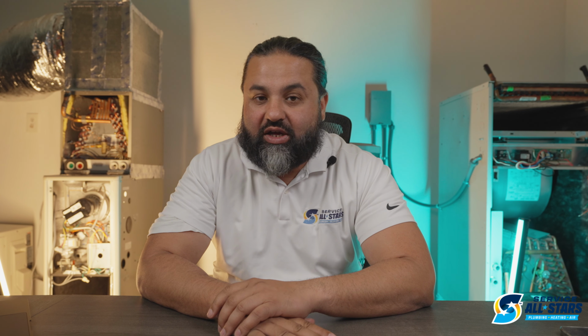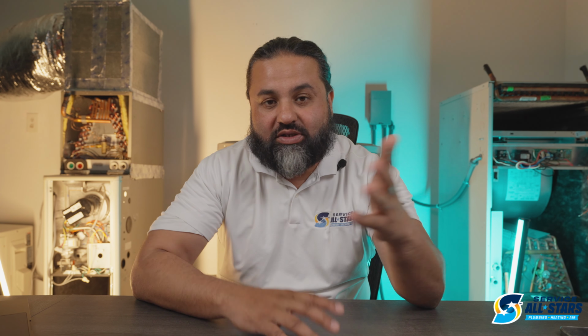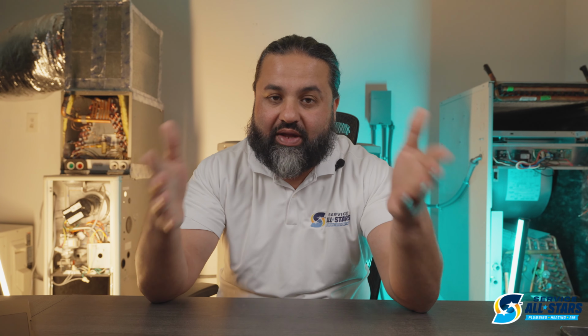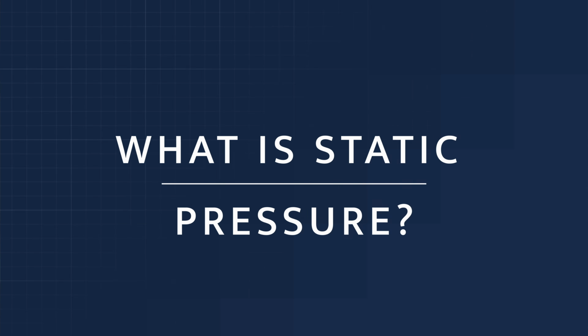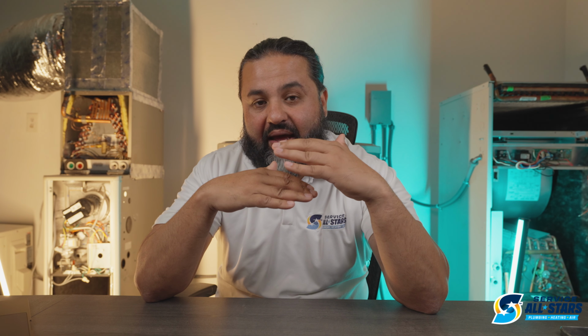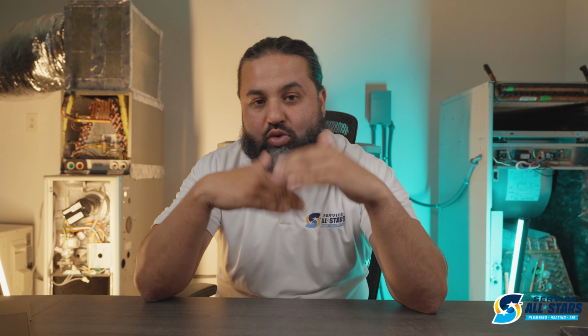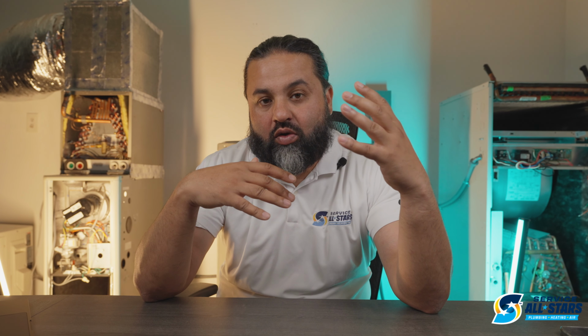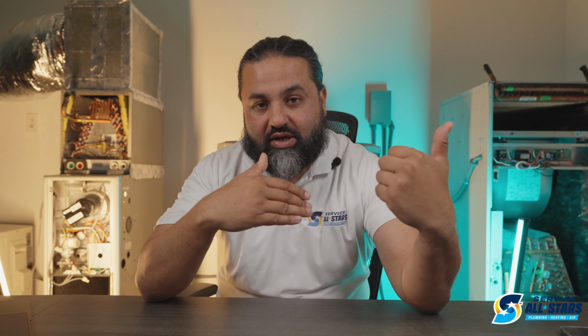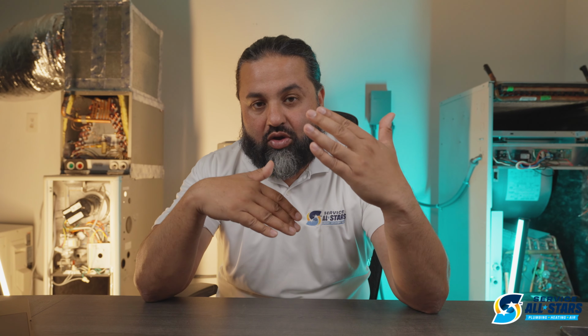Today I'm going to be talking about the importance of static pressure and how important static pressure is to these systems that are installed in your businesses and your homes that provide you the comfort that you deserve. Where we're going to start off is, what is static pressure? So static pressure is pressure that accumulates from the movement of the motor, airflow as the air gets sucked into the motor and then going forward out into the ductwork. It's all pressurized air, whether it's negative pressure or positive pressure.